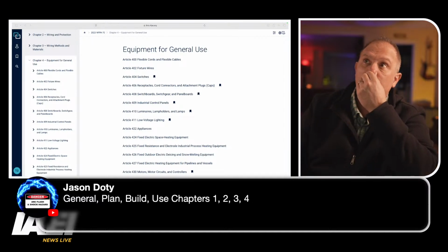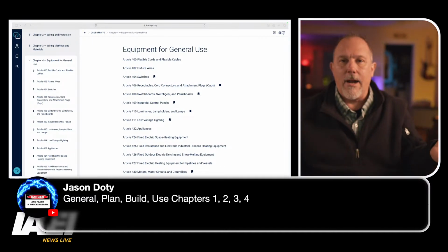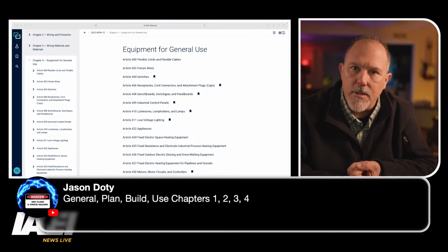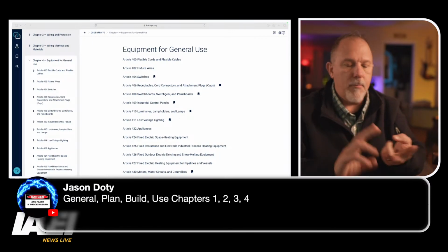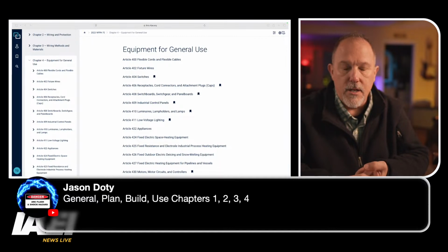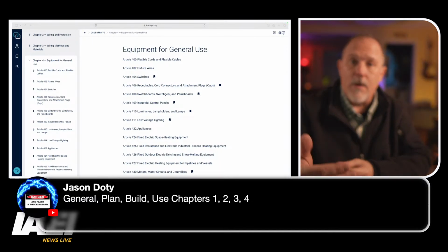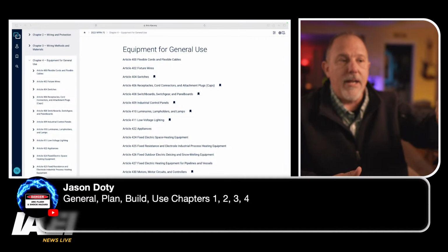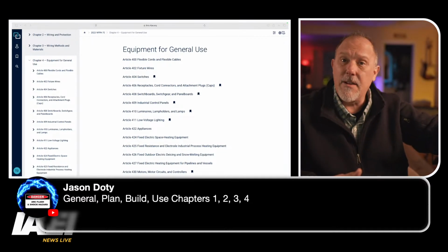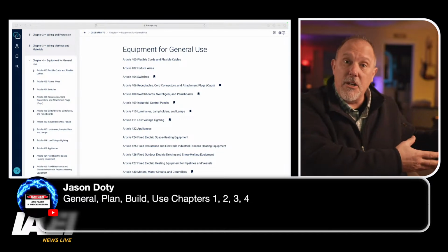So for most installations, anywhere you're going to land a wire, you know you're in 110 -- that's general requirements. You know you're going to be in Chapter 2, whether it be a branch circuit, a feeder, all that jazz, or service equipment, etc. When you get to Chapter 3, if it's a wire, you're going to need to determine ampacity, and figure out how you're going to route it -- do I need to put it in a raceway?